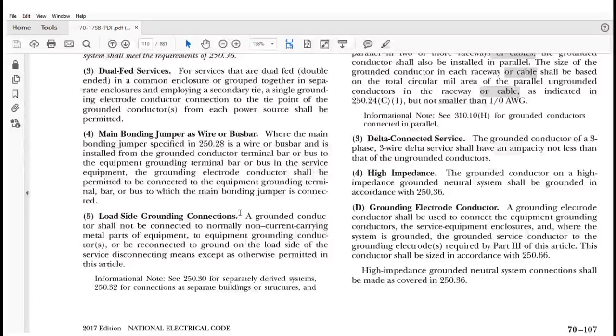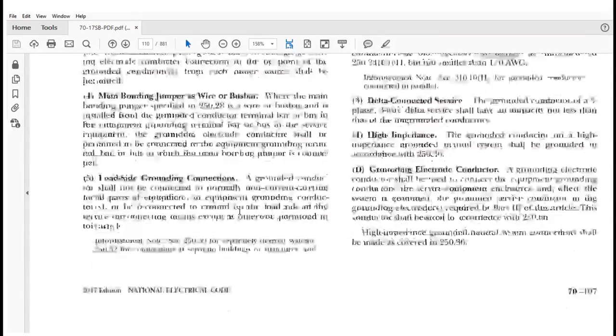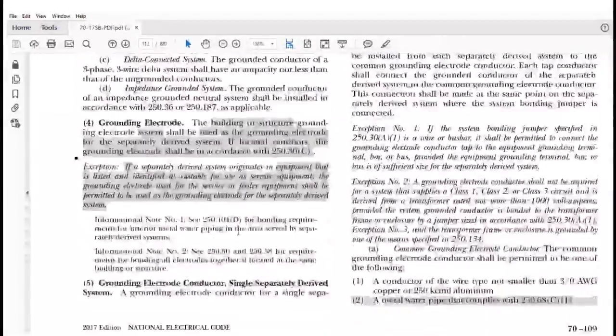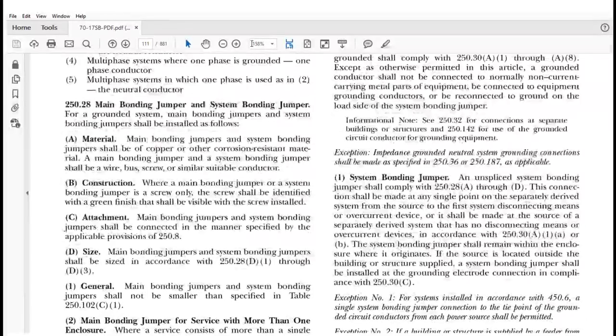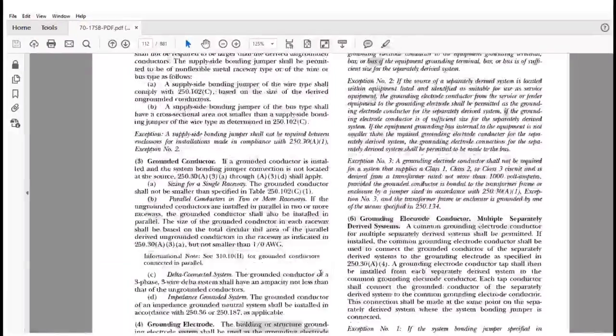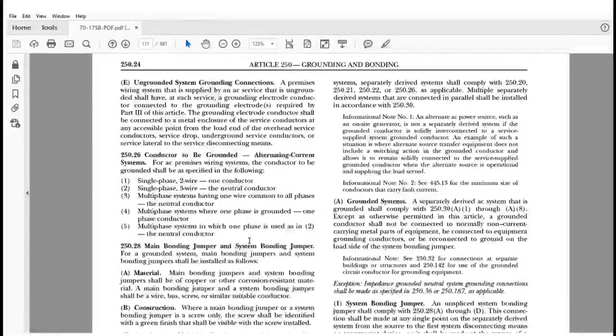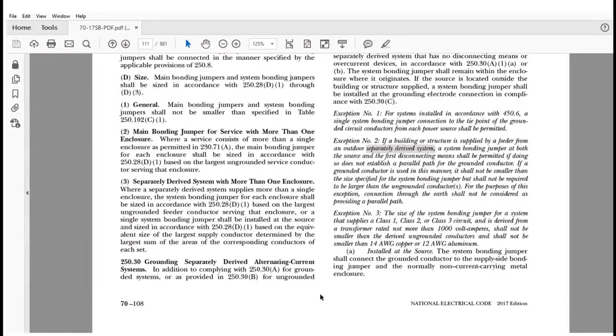The next change that we're going to look at is in 250.30(A)(4) and (5). So let's take our code book and go down to those areas of change. Got to bear with me, because let me make this smaller so we can see it all there. All right, so we're looking at 250.30. You know, I always said it would be easier to use the electronic version, but it is not, I can tell you right now. All right, so here, grounding separately derived alternating current systems. There has been a change in this application. One of the significant changes here is the use of metal water piping or building steel as the first option. Previously, when you have a separately derived system and you have to connect it to the grounding system, those were the steps that had to take place.